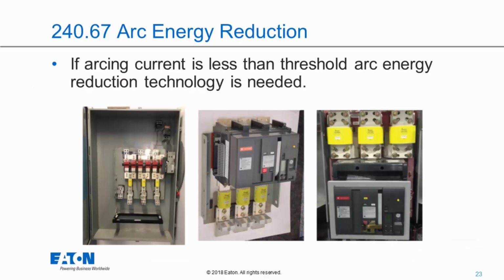So some options might be, and I have three examples here. The first option is the shunt trip switch with the arc energy reduction relay. That is what Eaton is currently offering. And basically the arc energy reduction relay provides a different curve for the lower values of overcurrent, as well as a maintenance mode, which would basically drop that to a rating of rated current of the capacity of the switch. So it'll provide that faster tripping time where needed. So the current would be detected by the arc flash relay and then tripped where appropriate. And then on the right, we have some high pressure contact switches from ABB/GE, and they basically have arc energy reduction technology in those high pressure contact switches.